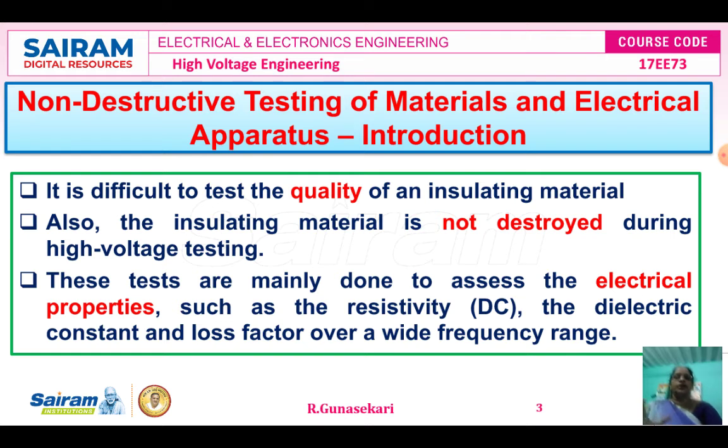Testing the quality of the insulating materials is very difficult. The insulating materials should not be destroyed during high voltage testing. These high voltage tests are mainly done to assess the electrical properties, that means the electrical properties like DC resistivity, dielectric constant and loss factor over a wide frequency range.